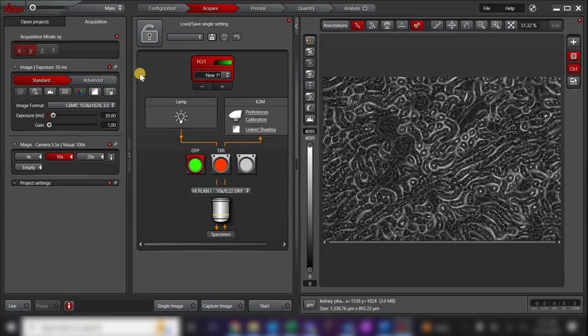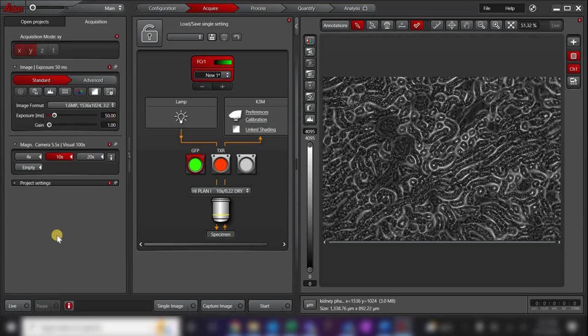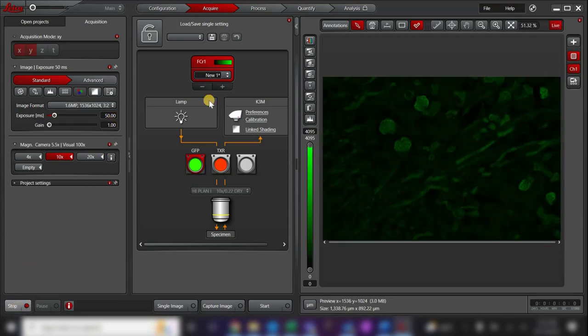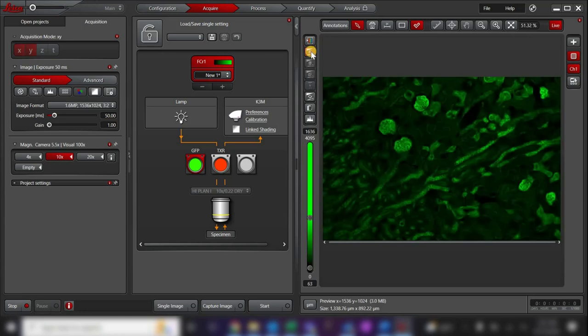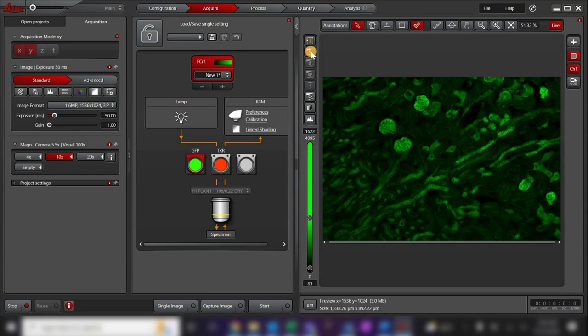Next, set an appropriate exposure time. The exposure time you set will be sample and experiment dependent. To learn more about setting an appropriate exposure time for fluorescence imaging, see our video on best practices for camera and illumination settings. Go live to view your sample. For fluorescence, we recommend using the autoscale feature to visualize dim signals and ensure you are not saturating your signal. Make any necessary adjustments to your sample, then press start when you're ready to take your image.